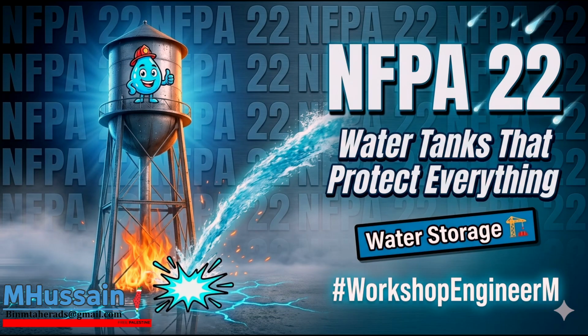And to find the coldest water, you have to understand thermal stratification and the density anomaly of water. The density anomaly. Yeah. Water is actually at its densest at approximately 39.2 degrees Fahrenheit. Right. As it cools toward freezing, it becomes less dense and floats. But a bulk mass of cooling water against the uninsulated steel shell will sink and stratify. The engineer must locate the thermometer precisely where that freezing water will accumulate. If that localized cold spot drops below 42 degrees Fahrenheit, alarms must trigger.